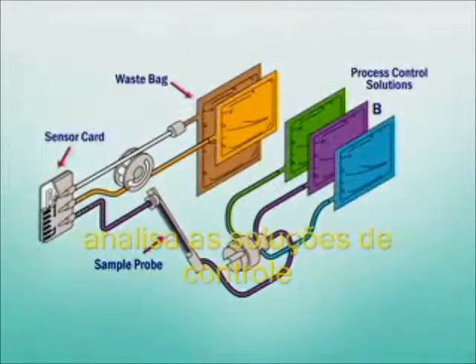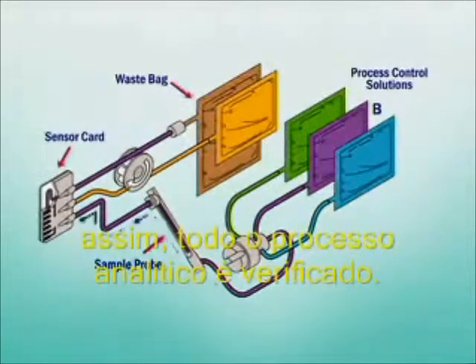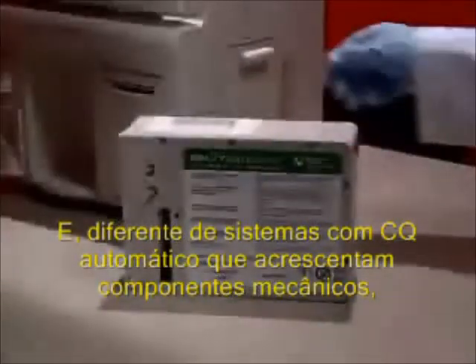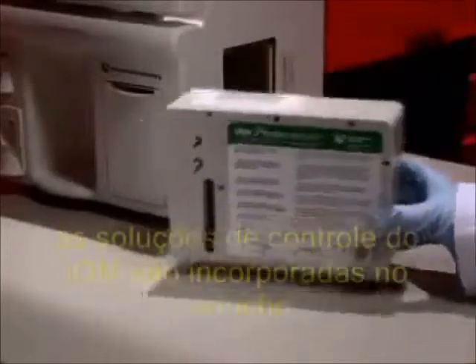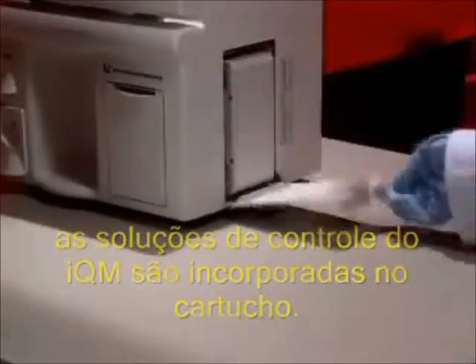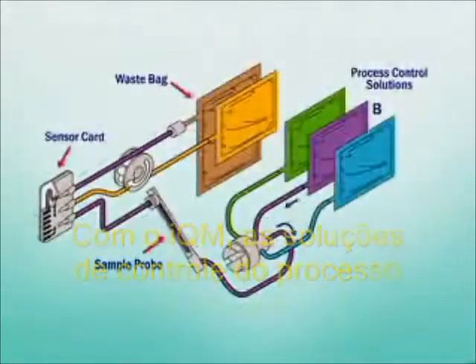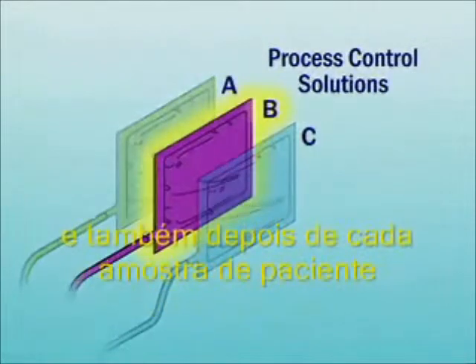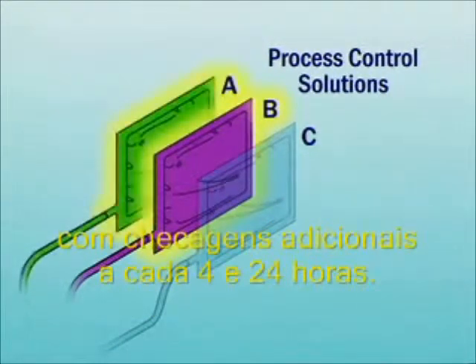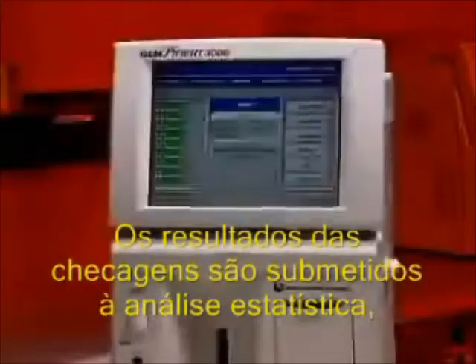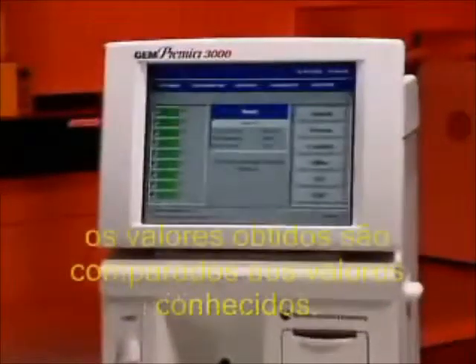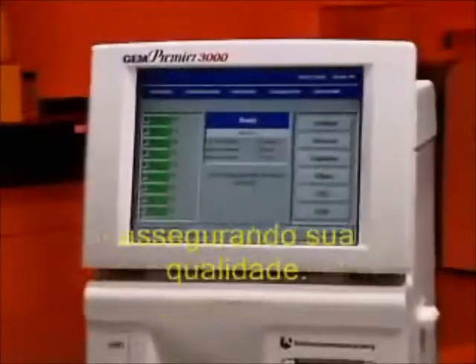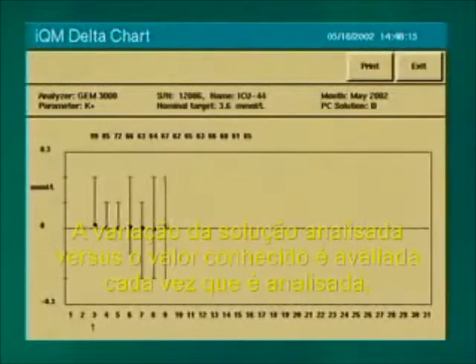Unlike systems that use electronic quality control, which may leave errors undetected, IQM's active process control analyzes process control solutions in the same way a patient's sample is analyzed, so the total analytic process is verified. And, unlike systems with auto QC modules that add mechanical components, IQM's process control solutions are incorporated into the cartridge. With IQM, process control solutions are automatically monitored every 30 seconds and run with every patient sample, with additional checks every 4 and 24 hours. The process checks are subjected to the same statistical analysis. The values of the process control solutions are compared to known values, further assuring quality. The delta of the process control reading versus the known value is evaluated every time it is analyzed.